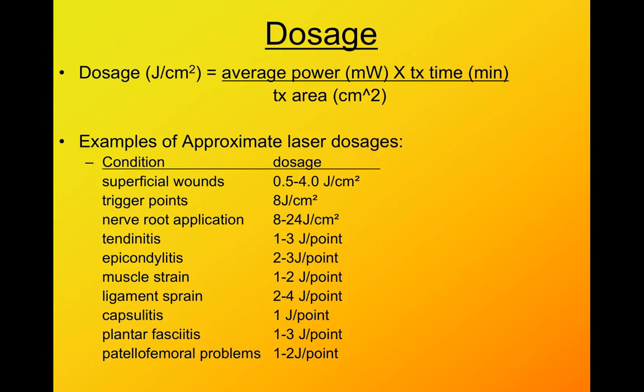So again, your treatment area is going to be the area of the laser beam or the area to be treated, and that's going to be in centimeters squared. And so that's going to end up affecting our power or our treatment time. And so typically our machines let you, the power is either set or you have very distinctive power outputs that your laser can do. So sometimes you can set a couple different ones, or it's just one set. So this is usually going to be set by the machine.